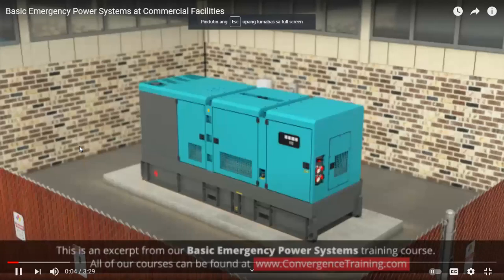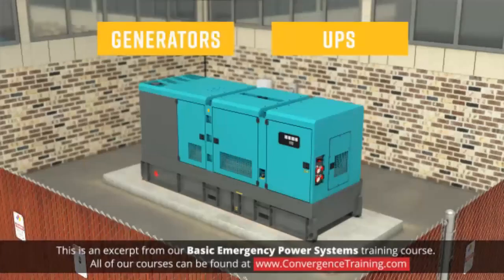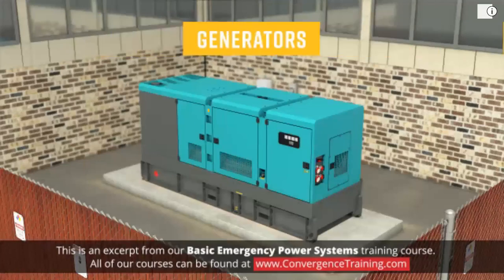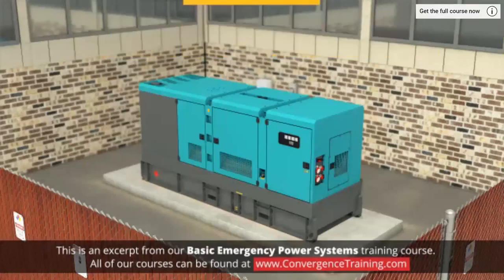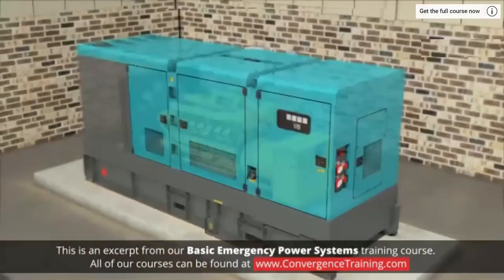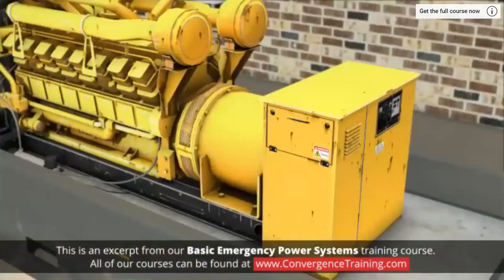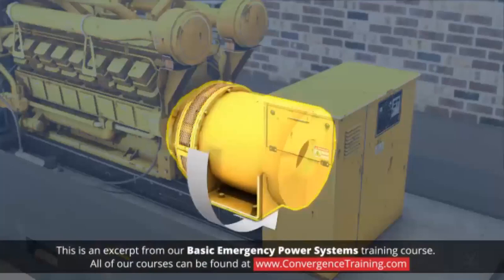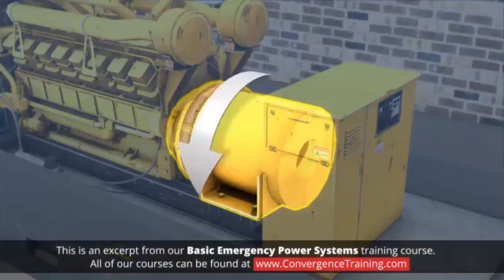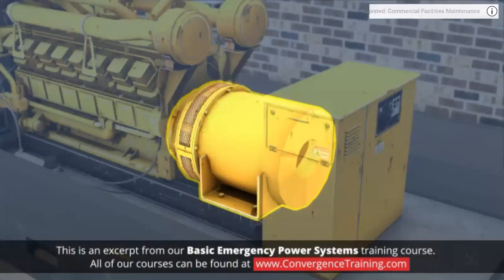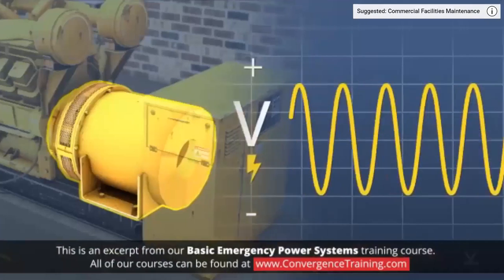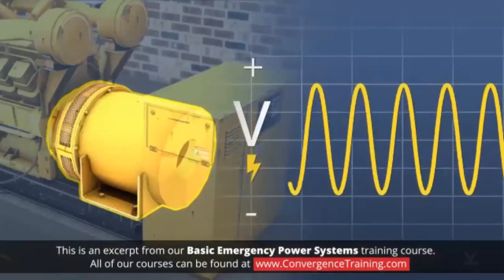There are really two major categories of widely used standby power systems, generators and UPS. I'm only addressing generators in this course. So, what's a generator? The generators in this course are a type of rotating machine, which, by design, generate electricity when rotated at a certain speed by some type of motor or engine. The generator portion of this system is generally a very robust, reliable device which, when operating, puts out up to a specified amount of current at a voltage consistent with the voltage of the system it is feeding.